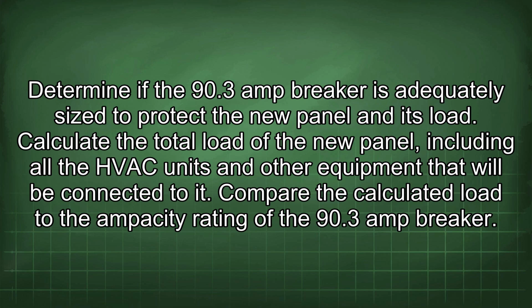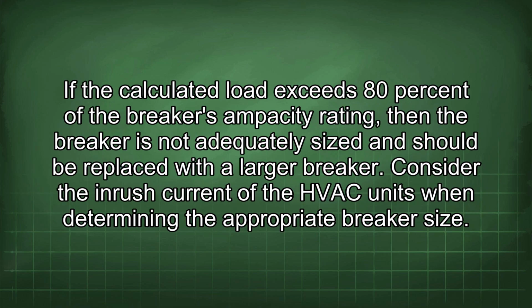Calculate the total load of the new panel, including all the HVAC units and other equipment that will be connected to it. Compare the calculated load to the ampacity rating of the 90.3 amp breaker. If the calculated load exceeds 80% of the breaker's ampacity rating, then the breaker is not adequately sized and should be replaced with a larger breaker.